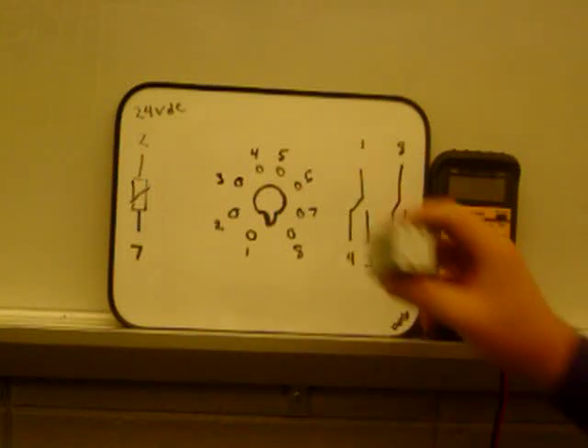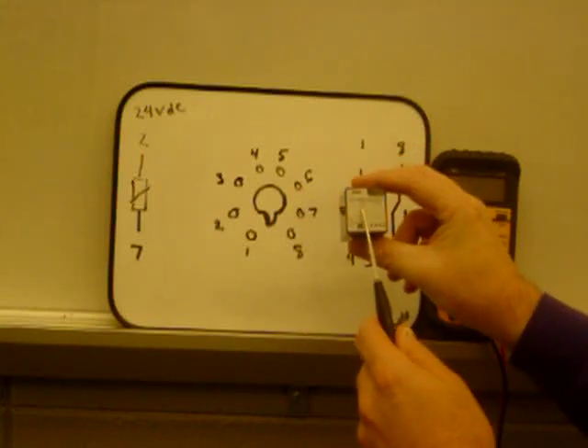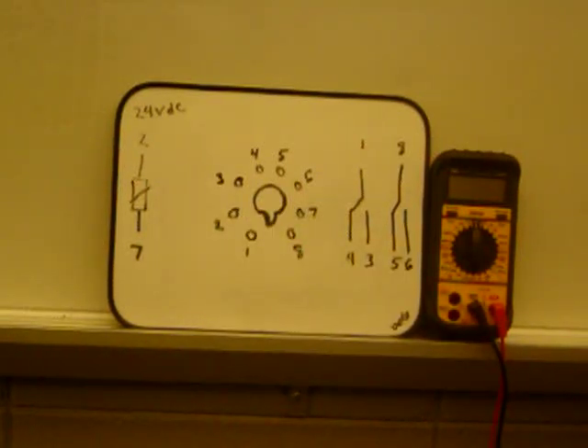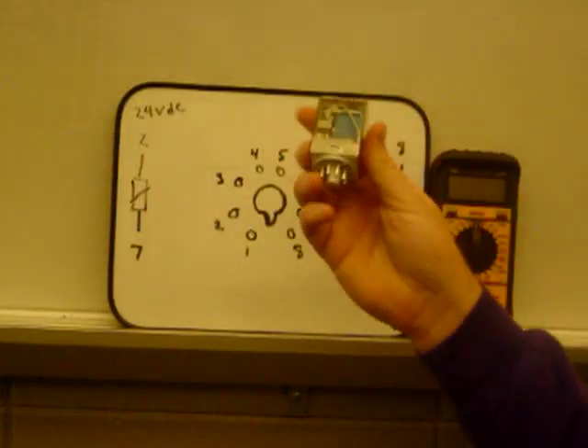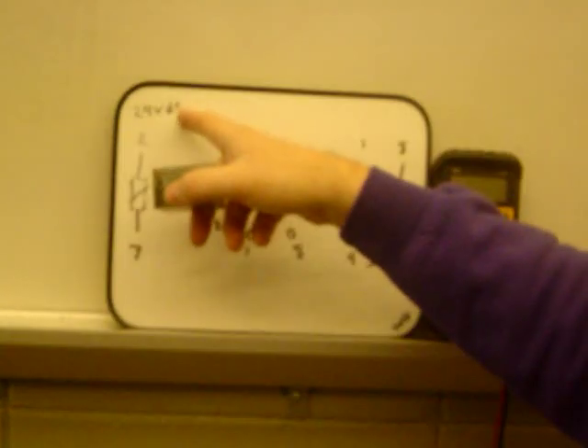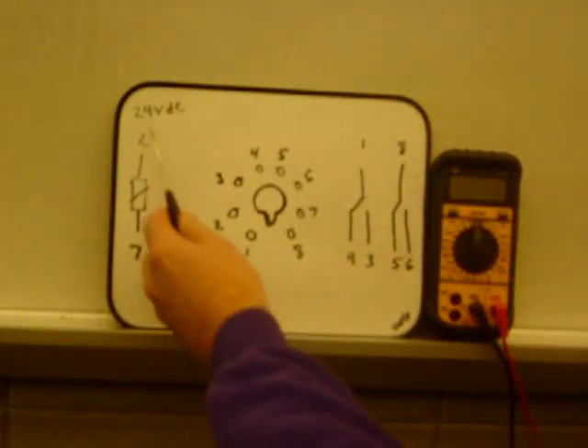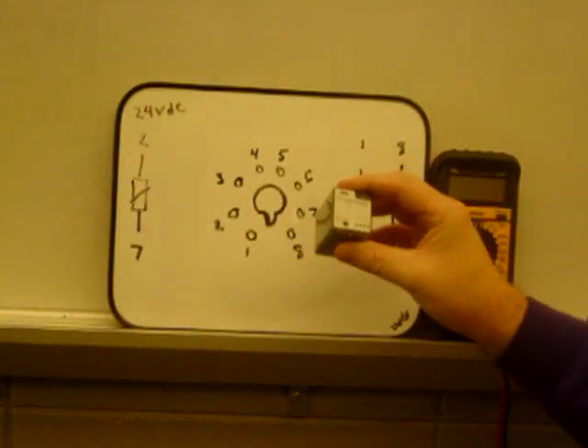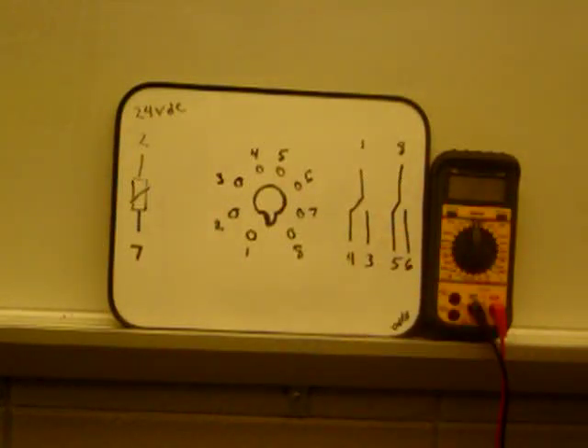Now it's important to always, when you take one of these relays, is to look for the coil voltage. In this case it says it's 24 volts DC. It's right here above the tube, and I wrote it out. These relays come in many different voltage values, so if you were to take out a 24 volt relay, put in 110 volt AC relay, it wouldn't work. So I've got DC relays, I've got AC relays, they're all going to look the same. The only thing that matters is somewhere on it, it will tell you what the coil voltage is. So anytime you replace a relay, you've got to make sure you get that right, because there are ones out there that are confusing.